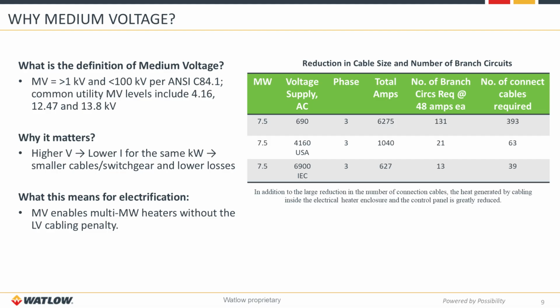The table on the right demonstrates the significance of moving from a 690 volt low voltage solution to a 4160 volt or 6900 volt medium voltage solution. You will note up to 90% reduction in the number of branch circuits or cables required when comparing a 690 volt low voltage solution to a 6900 volt medium voltage solution.